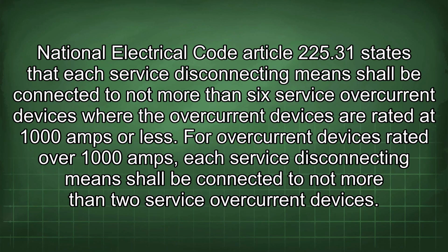National Electrical Code Article 225.31 states that each service disconnecting means shall be connected to not more than 6 service overcurrent devices, where the overcurrent devices are rated at 1000 amps or less. For overcurrent devices rated over 1000 amps, each service disconnecting means shall be connected to not more than 2 service overcurrent devices.